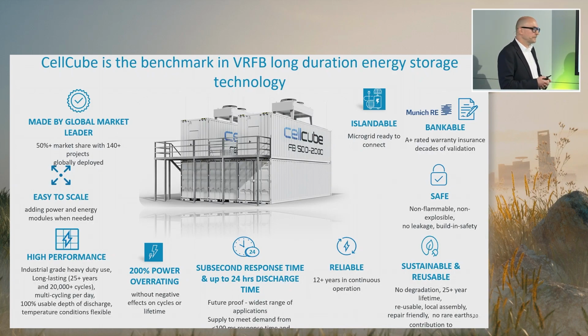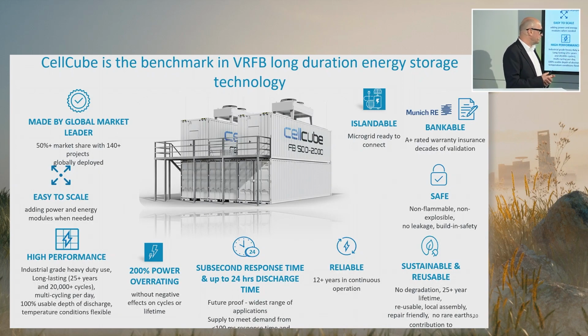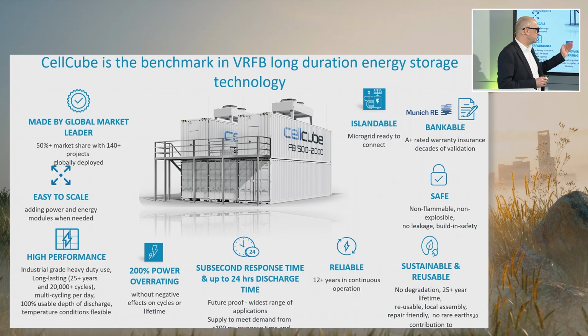The system has a lifetime of 25 years plus. We can use 100% of depth of discharge. I mentioned overrating already. It has no negative effects on cycles or lifetime. The chemistry itself has a sub-second response time, so the response time is really defined by the control loop and the inverter used. And we can have discharge times up to 24 hours.